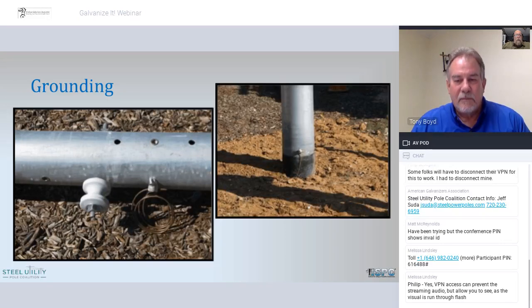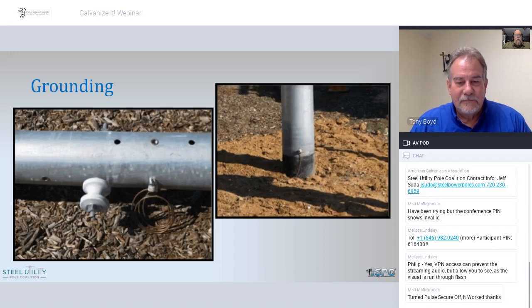And like Tony points out, every pole is different, and it depends on the environment that it's been in, how dry the wood is. Because I used to do the same thing on a 4 kV feeder, 4,000 volt feeder. If we had to change out an insulator, we would just take the conductor, untie it, and lay it right on the wood arm. And if it smoked, you just lift it up and put a leather glove under it. And that's how we treated it. And that is an error in judgment. It still should be covered, and we should not be taking anything for granted.